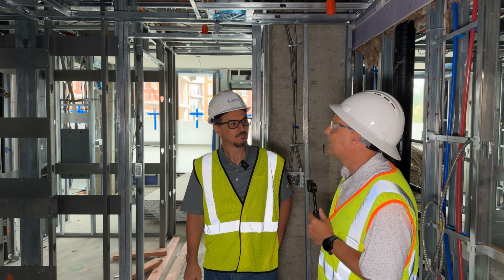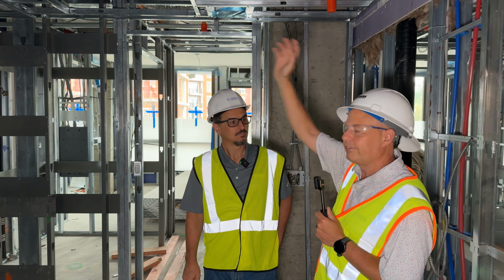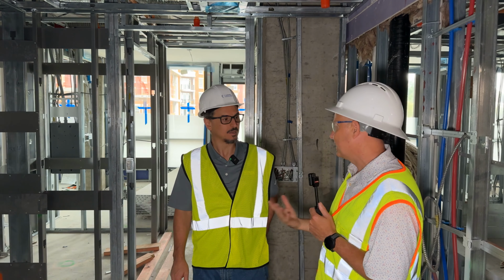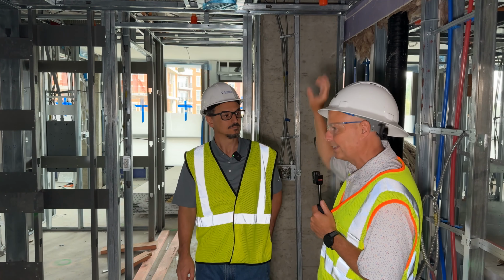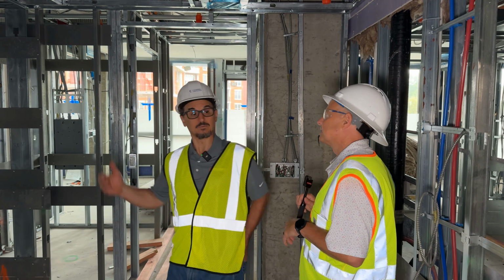But then the other problem is, if you duct it in, then all of a sudden you're relying on the fan of the fan coil to then help distribute that ventilation. Whereas if you just decouple it and let the DOAS fan handle that. I love it. Okay, so maybe we can walk through this.